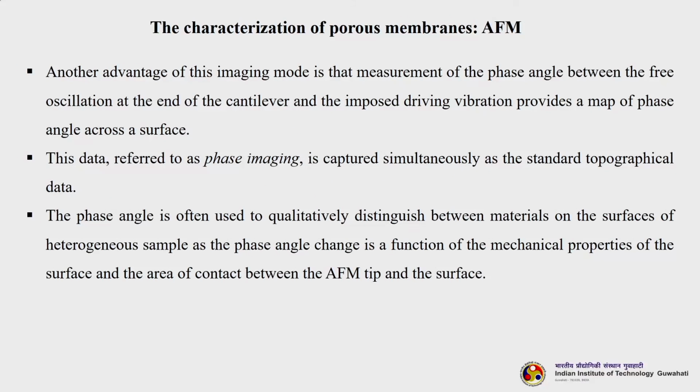So, an advantage of this imaging mode is that measurement of the phase angle between the free oscillation at the end of the cantilever and the imposed driving vibration provides a map of phase angle across the surface. This is referred to as phase imaging. This is captured simultaneously with the standard topographical data.